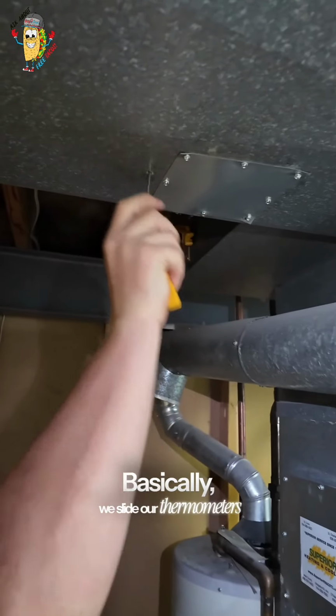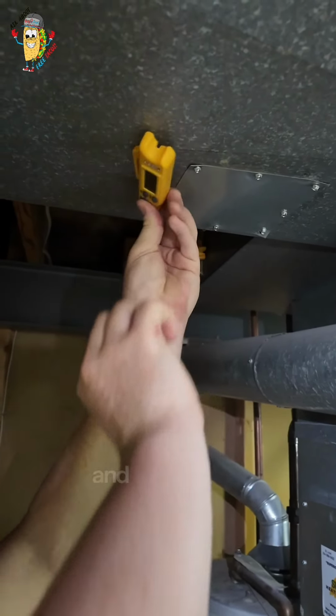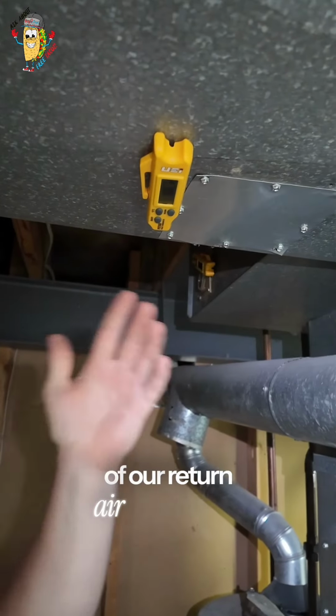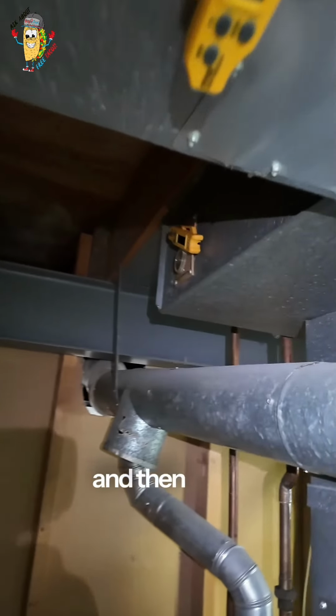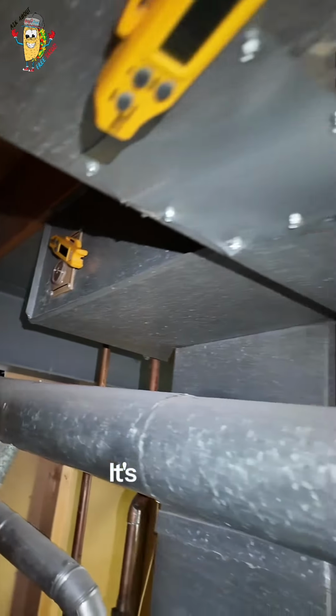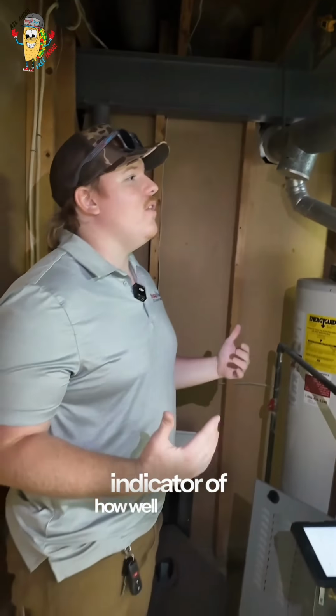Basically, we slide our thermometers into the ductwork like this, and we're taking the temperature of our return air and our supply air. We're going to subtract the difference, and that's going to give us our temperature rise. It's basically a good standard indicator of how well the furnace is operating.